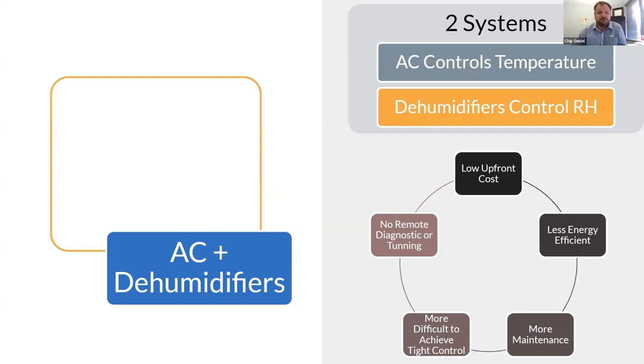I want to quickly go through these. With AC plus dehumidification, you've got two systems. One puts out cool air with some dehumidification, but really the design there is to cool the air. Then you have another system that takes the moist air and just removes the moisture. For each pound of moisture removed, you're adding 1,060 BTUs to the air, so you're just converting moisture to heat. Obviously, as you convert that moisture to heat, if you end up with too much heat, your air conditioning has to kick back on, so you've got two systems working to try and control.